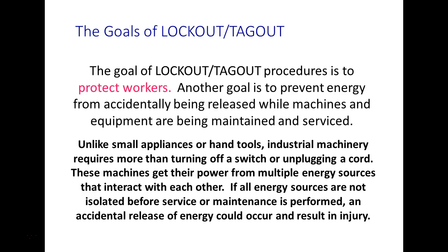What do you mean? Yeah, that's part of it, and this hadn't popped up yet. That's a common mistake, and it's going to be in these PowerPoints. Even though you cut the energy off, you're supposed to verify that it's gone, right? I understand that. A lot of our electrically activated disconnects depend on blades and this kind of stuff, and those things can get stuck, right? You have to do it with a meter or some other source. And for electricity, of course, the meter is what we would use. So what would we do every time we lock out the electrical? We would test it.